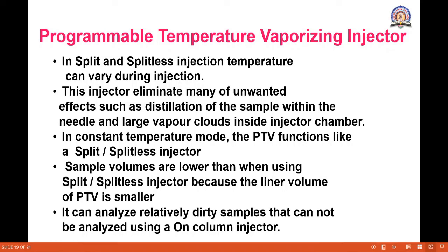That means the temperature variation condition is eliminated in this PTV injector, such as the distillation of the sample within the needle and large vapor clouds inside the injector chamber. Means these two conditions happen in the split and splitless injection, so they are minimized in this PTV injector.